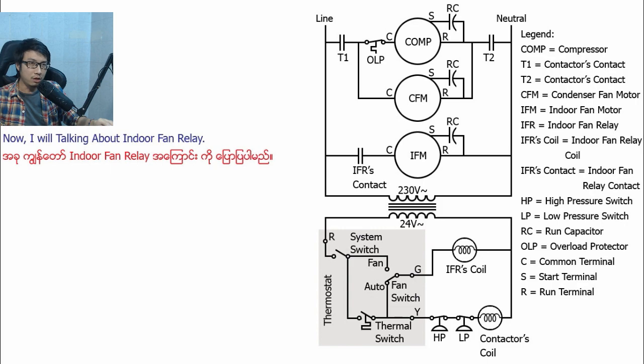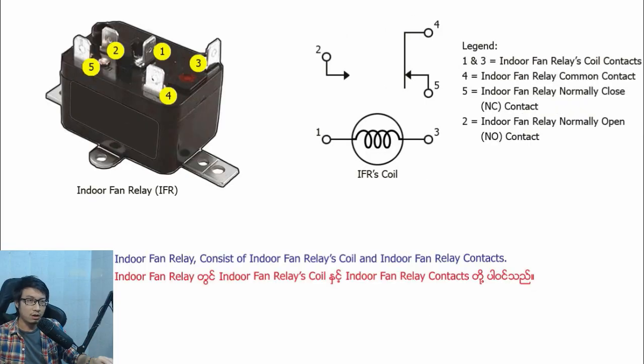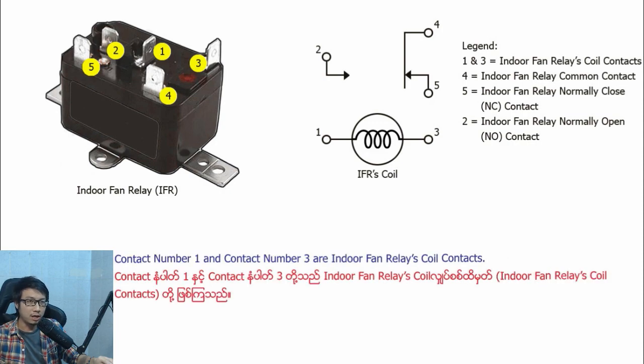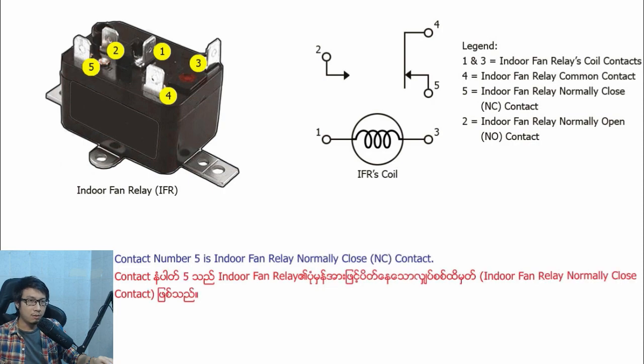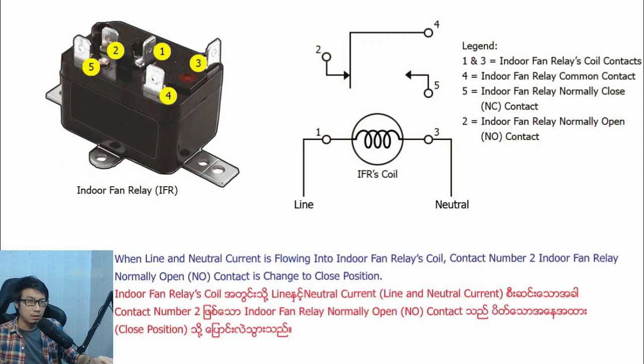Now I will talk about the indoor fan relay. The indoor fan relay consists of the indoor fan relay coil and indoor fan relay contacts. Contact No. 1 and Contact No. 3 are the indoor fan relay coil contacts. Contact No. 4 is the indoor fan relay common contact. Contact No. 5 is the indoor fan relay normally closed contact. Contact No. 2 is the indoor fan relay normally open contact. Contact No. 2 is the indoor fan relay normally open contact, which is changed to the closed position.